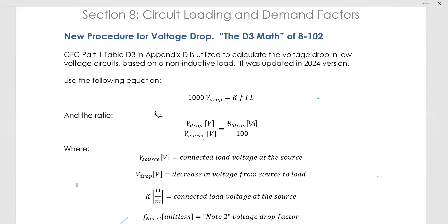You're going to comment below if you would like me to do a bunch of example problems for this in another video. In order to solve voltage drop problems for the Canadian Electrical Code Section 8, 8-102 voltage drop rule, you simply use this equation: 1000 times voltage drop equals factor K times factor F times current times length.